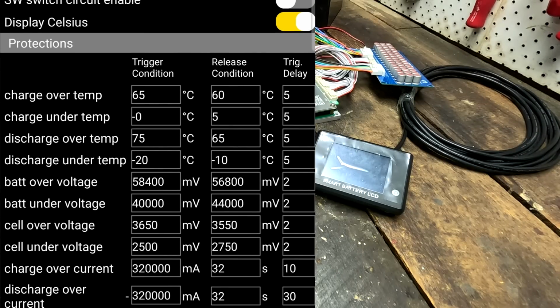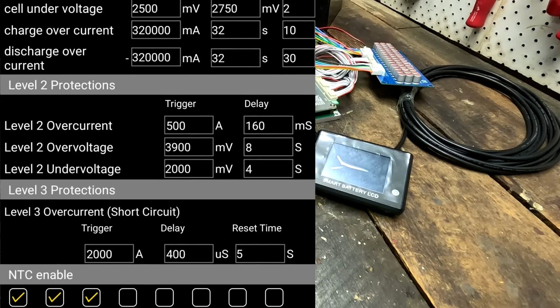Down here we can set all the protection parameters for charge over temperature, charge under temperature, discharge over, discharge under, and so on. Down here we have the level 2 protection: overcurrent, over voltage, and under voltage, which is already preset. Level 3 is short current protection, 2000 amps for 400 microseconds - it recognizes there's a short and turns off the MOSFETs as well.